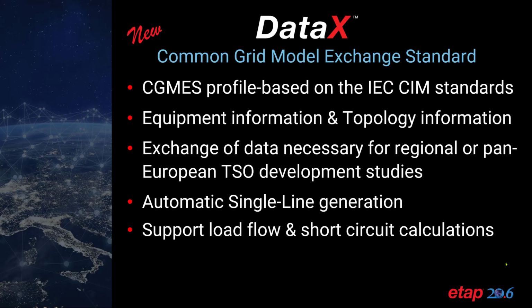Data exchange has been enhanced to include a new exchange capability, which is Common Grid Model Exchange Standard. CGMES profile based on the IEC CIM standard is prescribed by the European TSO organization, and it is a standard for the exchange of data necessary for regional or pan-European studies. By using the CGMES CIM profile, you can import the equipment information and topology, automatically generate a single line diagram, and we currently support load flow and short circuit calculations as means of this import.